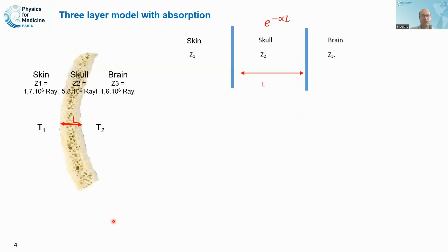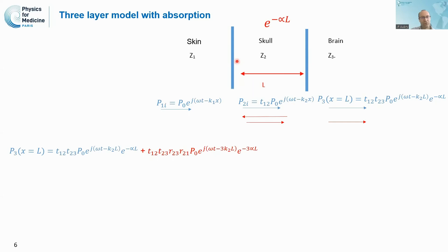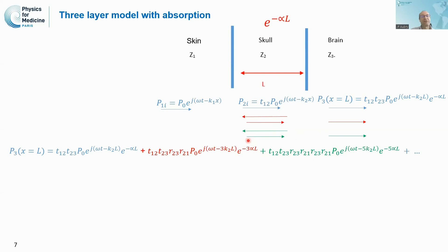What we did is model the skull as a three-layer model — skin, skull, and brain — and we considered the impedance mismatch but also the absorption inside the skull, and estimated the transmission of pressure. There is a first term based on the transmission of the wave through the skull, and then we take into account the reflections inside the skull, which suffer from each interface and from the absorption of ultrasound crossing the skull three times, and then the third reflection and third transmission through the skull.